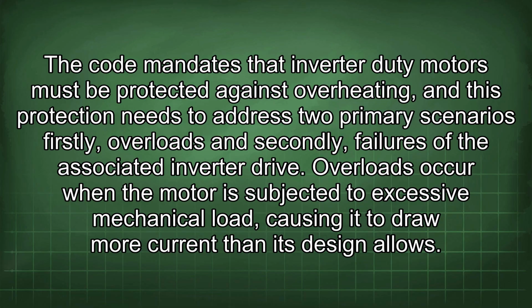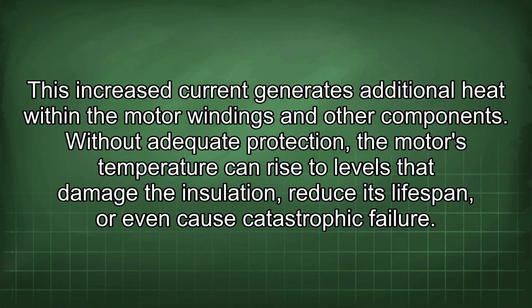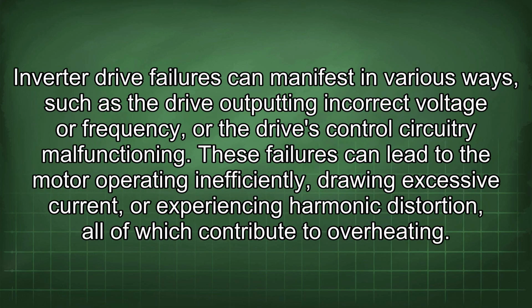Overloads occur when the motor is subjected to excessive mechanical load, causing it to draw more current than its design allows. This increased current generates additional heat within the motor windings and other components. Without adequate protection, the motor's temperature can rise to levels that damage the insulation, reduce its lifespan, or even cause catastrophic failure. Inverter drive failures can manifest in various ways, such as the drive outputting incorrect voltage or frequency, or the drive's control circuitry malfunctioning.